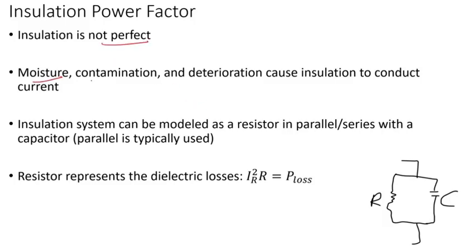There can be moisture and contamination. Insulation deteriorates over time and can cause the insulation to conduct current, otherwise creating a conductive path. The insulation system can be modeled as a resistor in parallel or in series with a capacitor, and typically the parallel model is used.